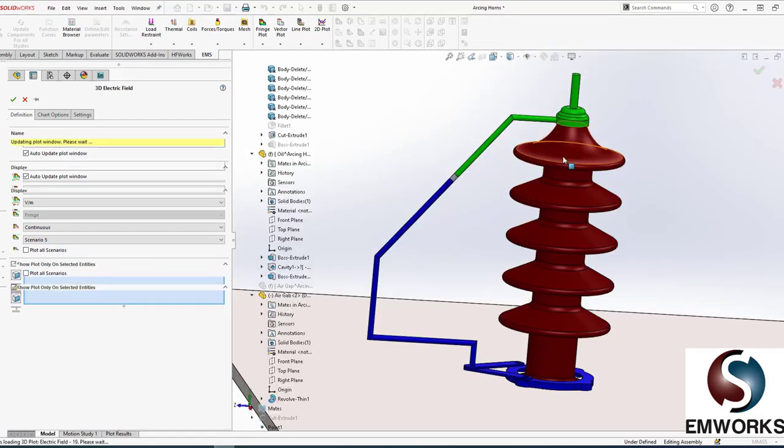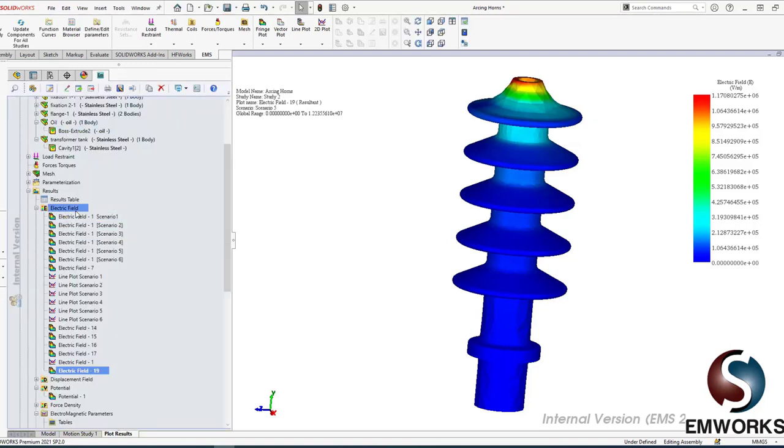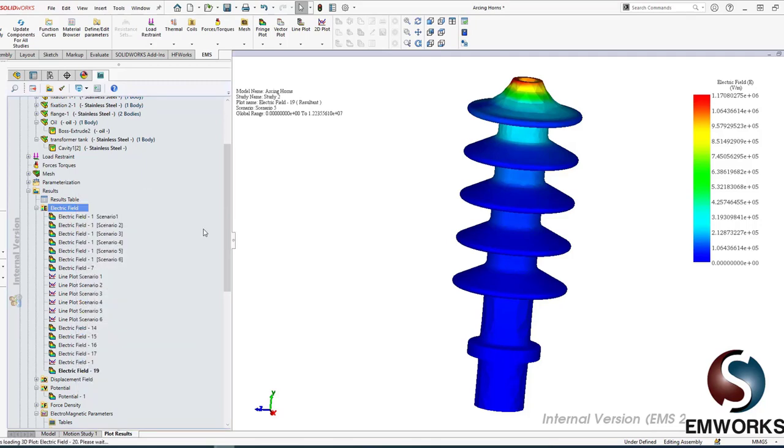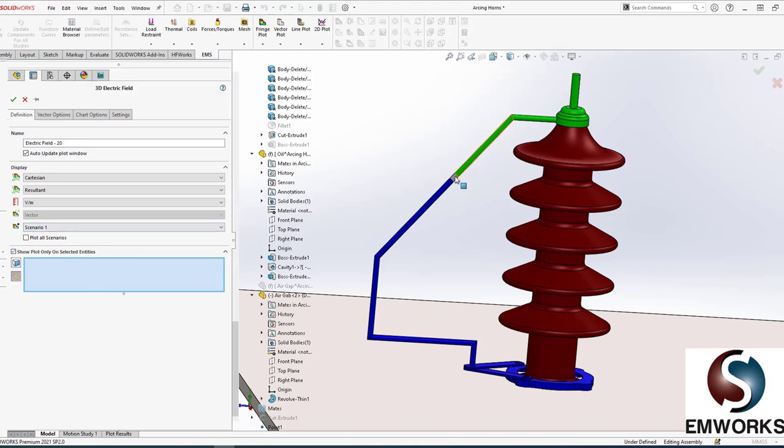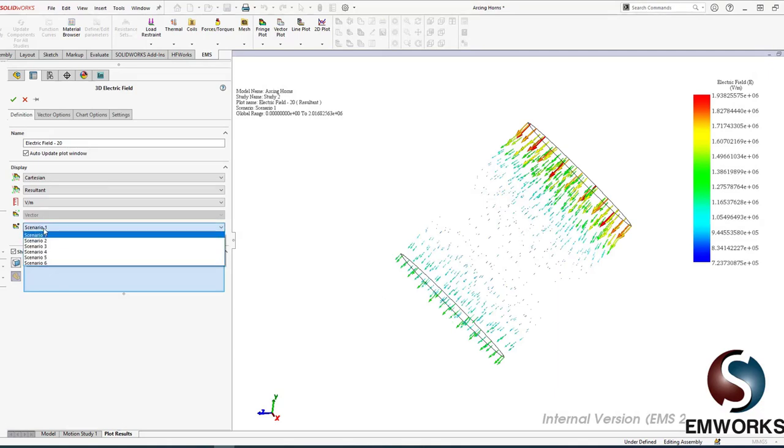Scenario five, plot in the insulator. Zoom to fit. Now, am I going to have a breakdown? No, I'm not going to have a breakdown. So this is a good design at this dimension of the air gap because the insulator is safe and the corona—if I want to, I can put a vector plot to probably better show the corona in the air gap. And there you go, so your corona. This is scenario one, but let's do scenario five.